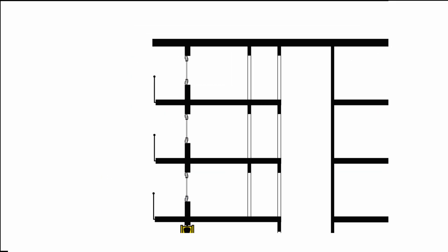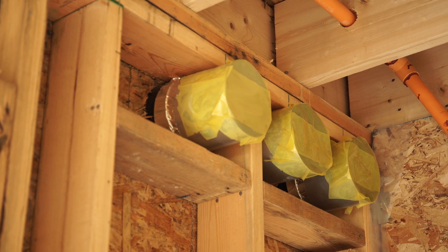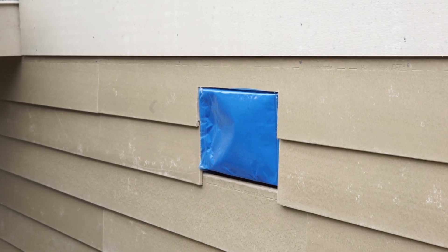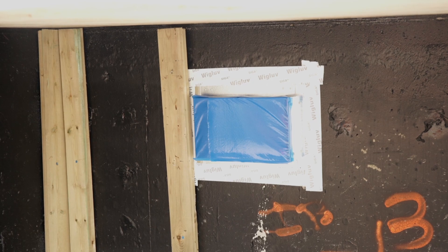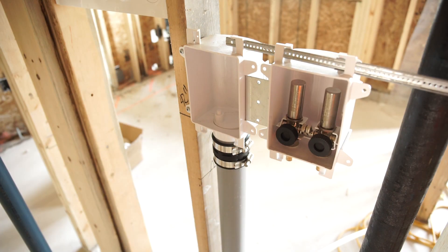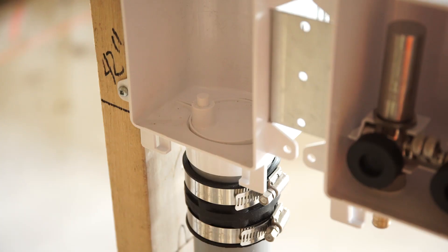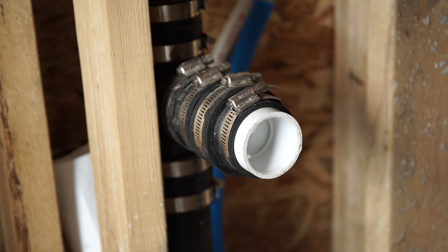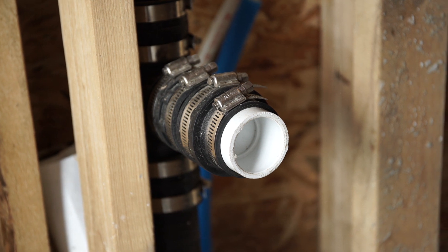Service and mechanical openings throughout the building air barrier system usually require temporary air sealing so they are excluded from the testing. Sealing openings are one of the most important aspects of test preparation, and this work is usually done by the construction crew. Temporary air seals must be robust enough to resist the induced pressures during testing. Painter's tape is not robust and should only be used to protect finishes beneath temporary air seals. Temporary air sealing also includes ensuring all plumbing drain pipes are sealed and P-traps are filled. This work can be time-consuming, so allow adequate time for building preparation prior to testing.